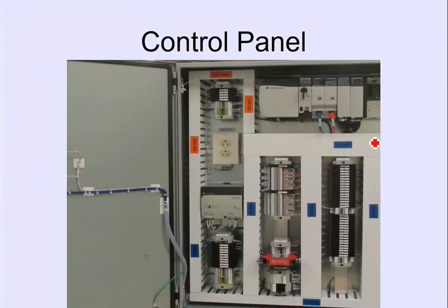Okay, how does it look on the control panel? Here is the place of the PLC. These are the terminal blocks. This is the SMPS. This is the backplane power supply, which is distinct from this bulk power supply. The SMPS is the bulk power supply. These are power connections, a 120 volt bus bar. This is additional power available. And these are the TBs in order to interface the field. You can see here the connections for remote IOs, right? These are the communication modules or cards.